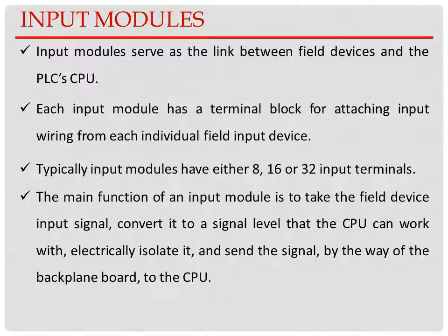Typically, input modules have either 8, 16 or 32 input terminals. The main function of an input module is to take the field device input signal, then convert it into the signal level that the CPU can work with, then electrically isolate it and send the signal by way of the backplane board to the CPU.